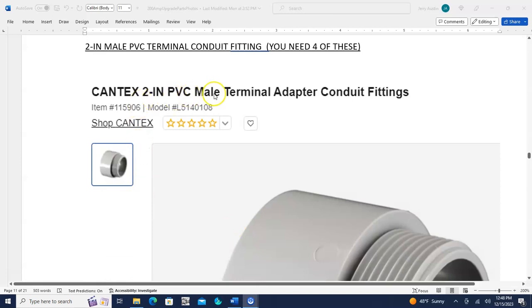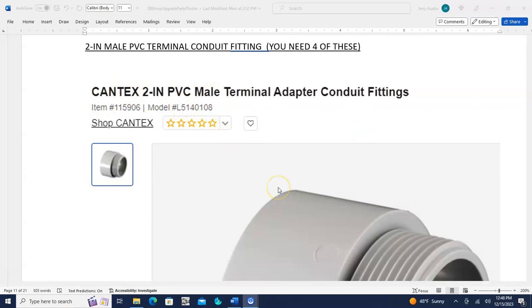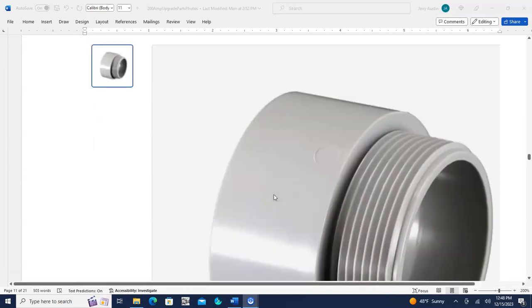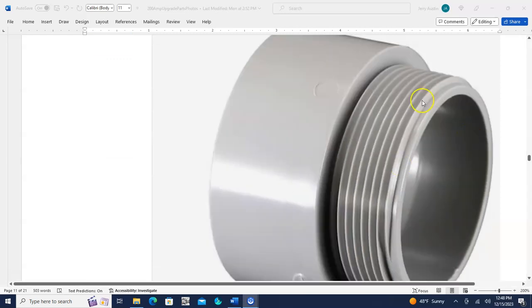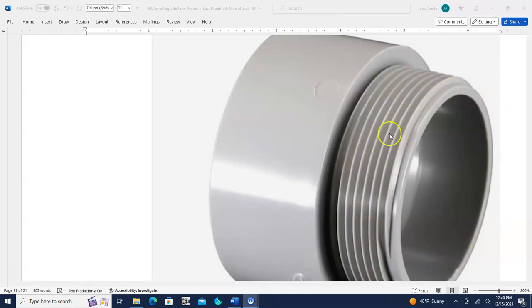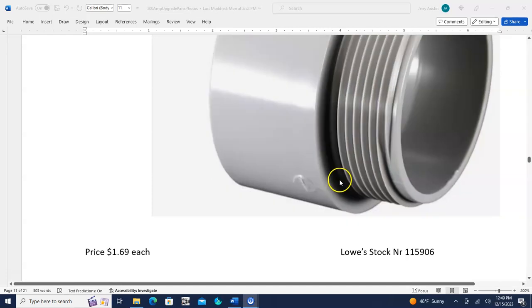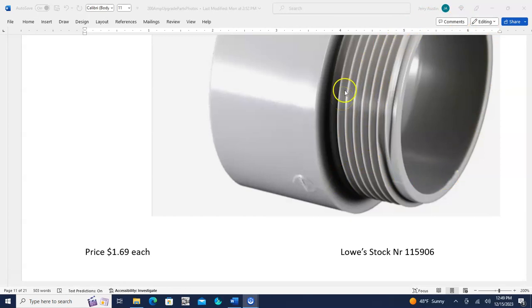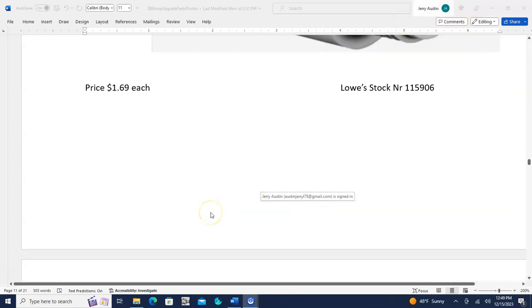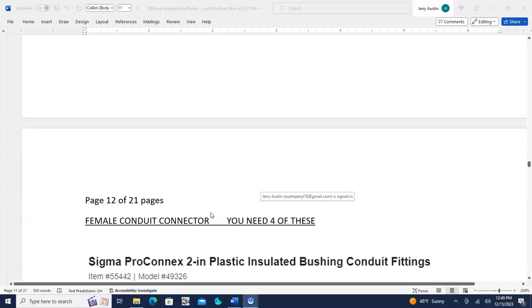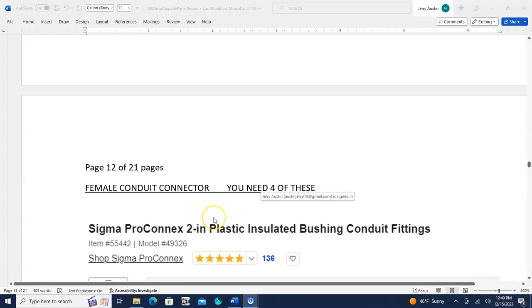This is a connector for that conduit, or you fit it into the circuit breaker box. There's a knockout on the side of the circuit breaker box, you just knock out the right one that fits right through. Then you've got a little steel connector, a steel cap that fits on top, tighten it down real good, and then a plastic cap fits on top of that to keep the wires from being chewed into by the metal.